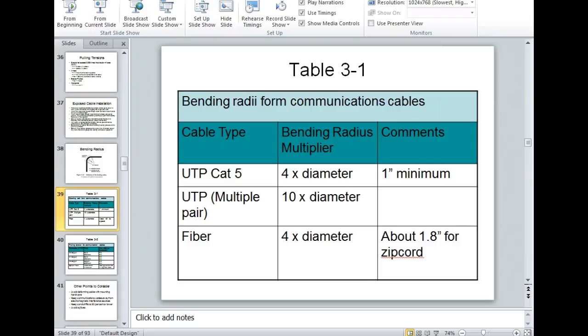We've got to honor the bending radiuses on these communication cables. If we bend them too much, we're going to change the characteristic impedance of the cable. And of course, terminating them and splicing them are very, very critical.